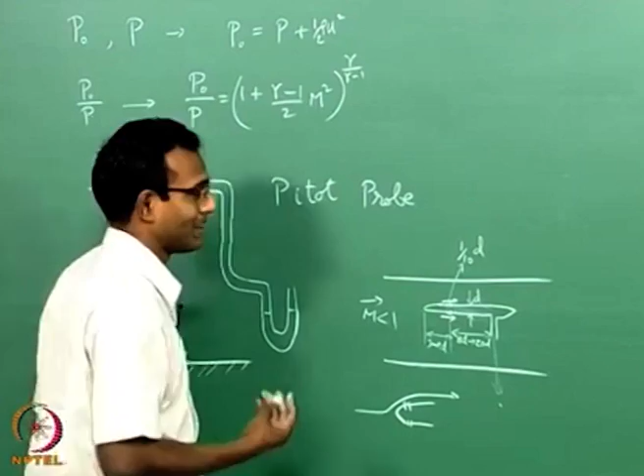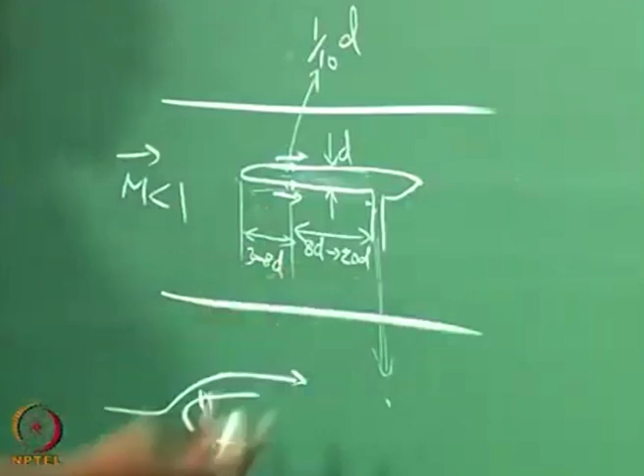Why do I have to worry about this length from here to here? Now I have to think about this flow going and stopping in front of it. I am going to create a stagnation point in front of this, which means pressure from here is, this is subsonic flow, right. So, pressure is going to increase immediately from here till it reaches there, so that the flow is adjusted by the time it reaches there. Subsonic flow typically does that, it adjusts to the incoming flow. So, it will start adjusting from here itself. So, I will get wrong reading unless it is so far out. Typically people keep it more than 10D, so that things are not interfering there. These are two things.